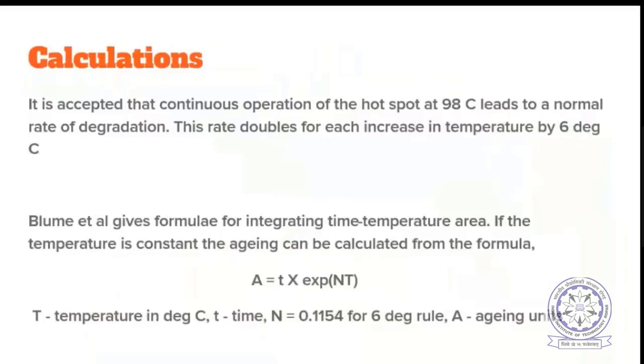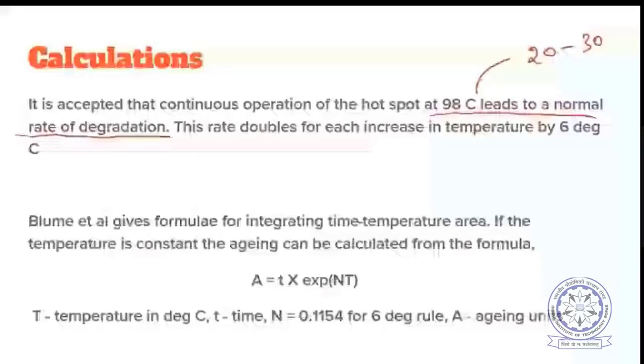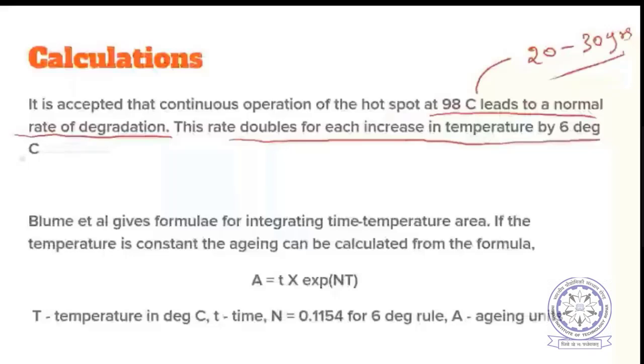Now, as per the calculations, it is accepted that continuous operation at a hotspot temperature of 98 degrees centigrade leads to a normal rate of degradation, which means 20 to 30 years of life. So a hotspot temperature of 98 degrees centigrade would lead to normal aging, meaning the transformer can survive 20 to 30 years without any problem. This is what is accepted in general. And this rate is accepted to double for each increase in temperature of 6 degrees centigrade. That is the 6 degree rule. So this is what is accepted.